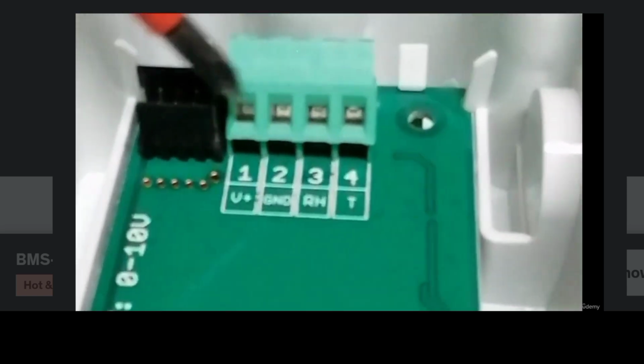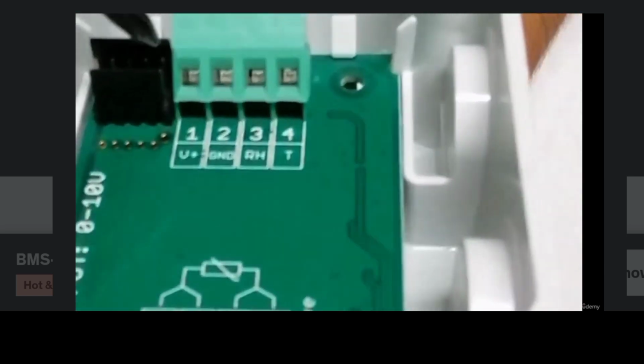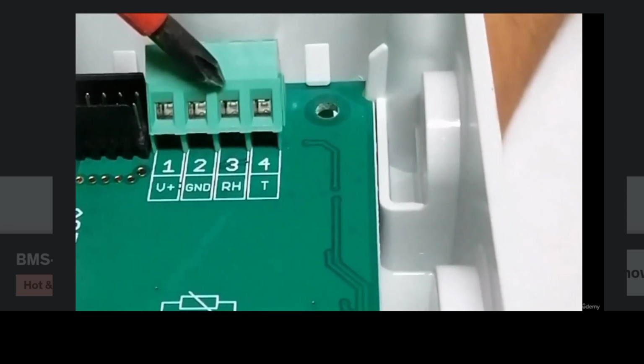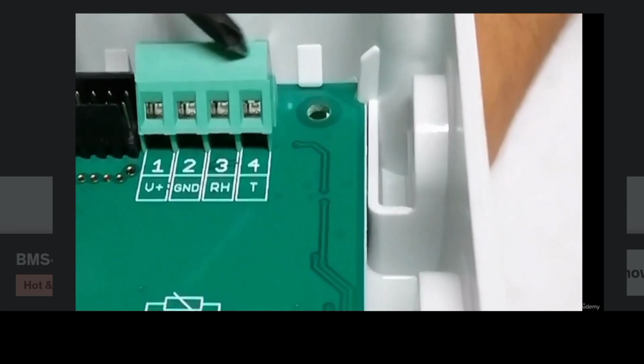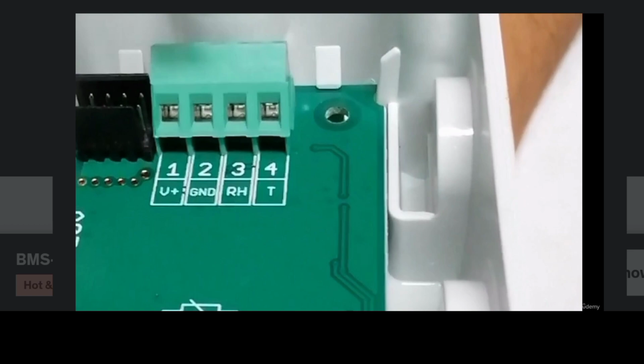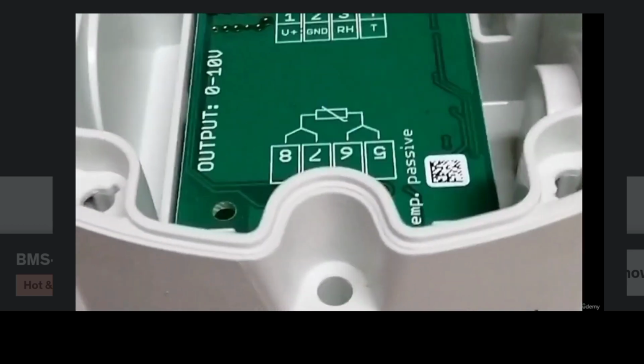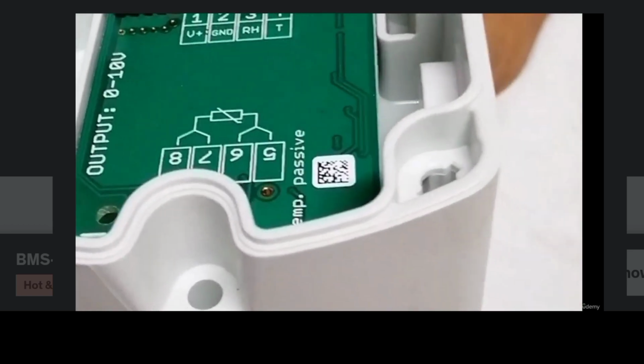Regarding the connections, here we have numbers 1 and 2, where we need a 24 volt DC or AC power supply. On number 3, we will get a 0 to 10 volt signal for humidity. And on number 4, we will get a 0 to 10 volt signal for the temperature. So this is an air temperature and humidity sensor for installation inside ducts.